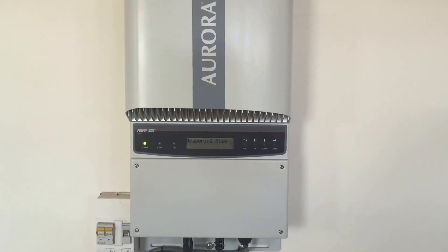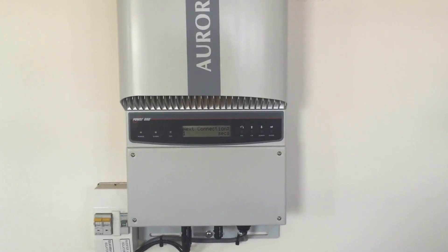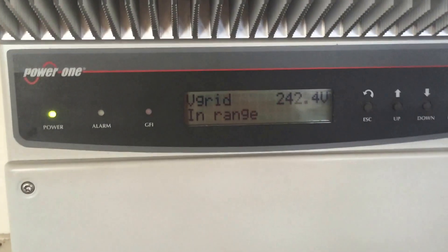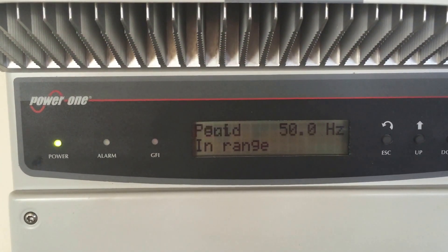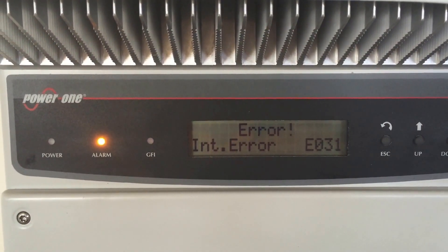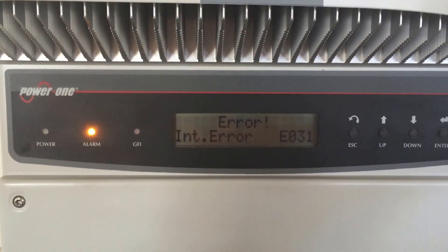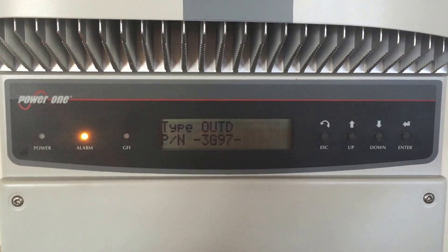Here we have an Aurora 3.6 kilowatt inverter that's been having an issue with an internal error. If you have a look at the screen here, you'll see it come up in a moment — you can hear the relay trying to pull in. There we go: internal error E031.